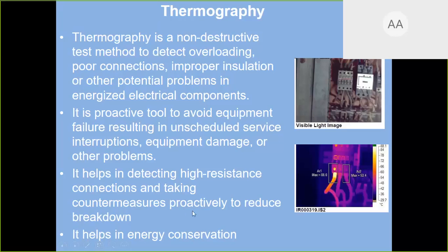High resistance connection means it will detect if there is resistance failure or high resistance where current is drawing more than the required capacity, because each wire has a current carrying capacity. Right? If the current carried is more, it will get overheated. Because of overheating, the insulation gets burnt. With this insulation material, there is a fire in the panel, and slowly it spreads to other areas if it finds any flammable or combustible item near the panel. So it will help in detecting the high resistance connections and taking countermeasures.